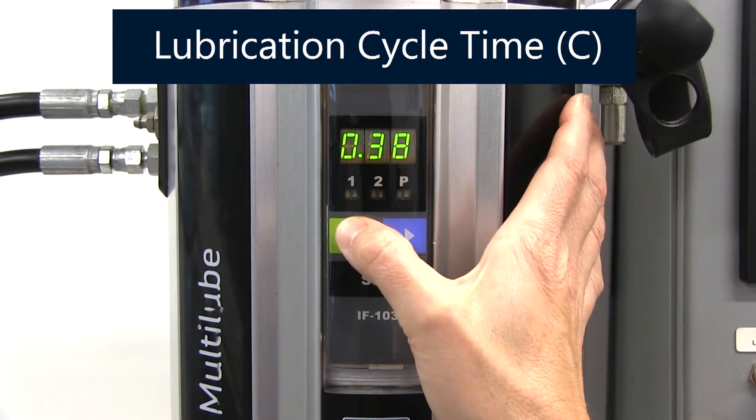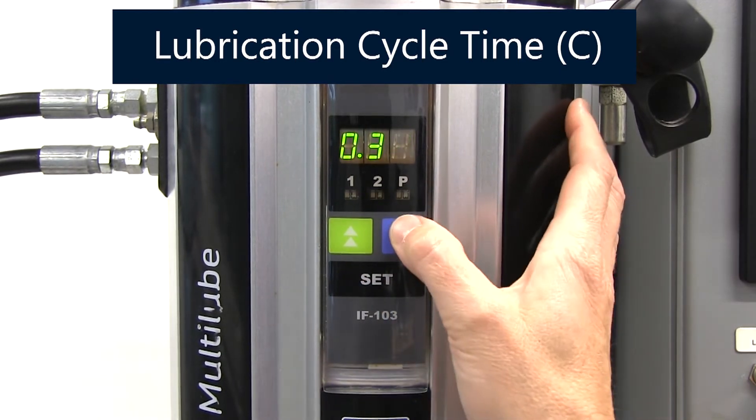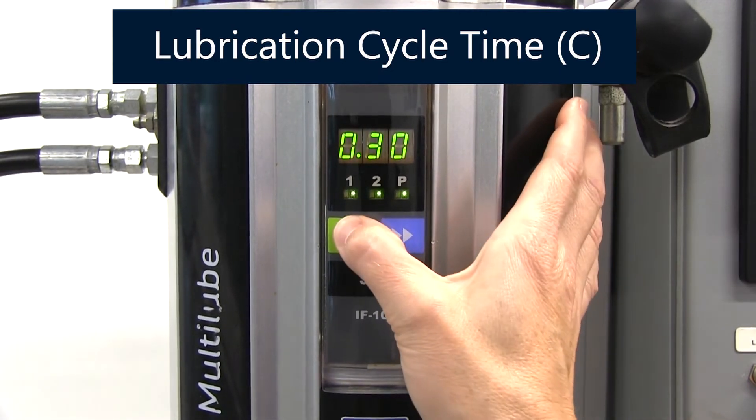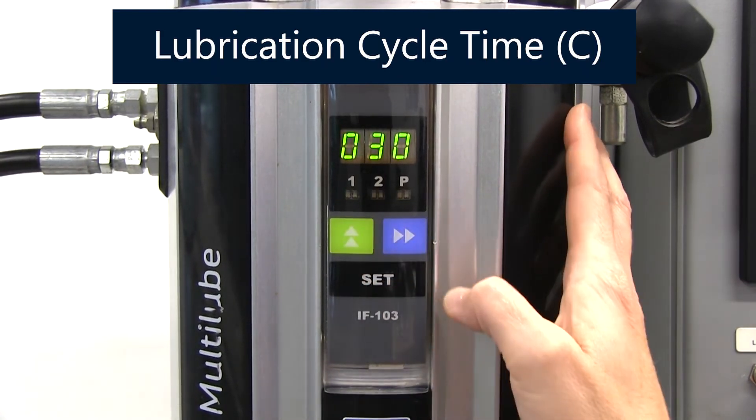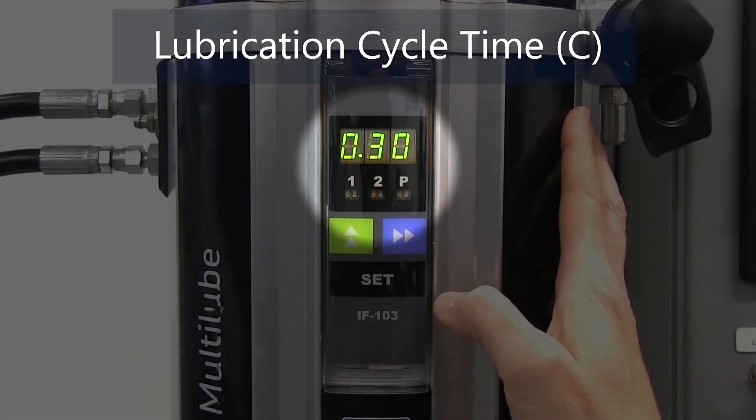Press the blue right arrow button once more after the rightmost digit is selected and use the green up button to adjust the decimal location. In this case, we are setting lubrication cycle to 30 minutes, so we want 0 decimal 3 0 to indicate 0 hours and 30 minutes.